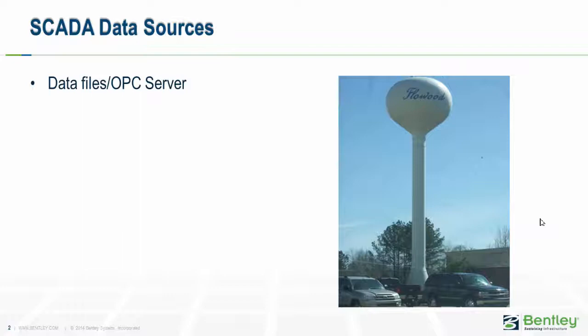This is the server that accepts the data from the communication system and serves it up to the SCADA human-machine interface and historians and other SCADA features. So there are two ways to get to data. We're going to also talk about the SCADA element. This is a modeling element that we now have in WaterGEMS and WaterCAD that actually represents the SCADA signal. So it's this element that will appear in the model, but instead of being a physical thing like a pump or a pipe, it is just a signal.